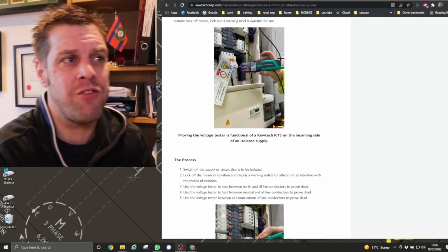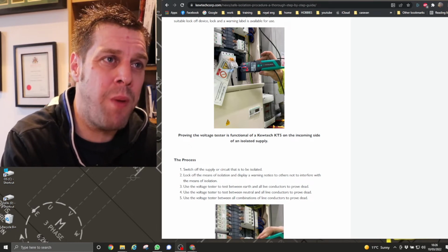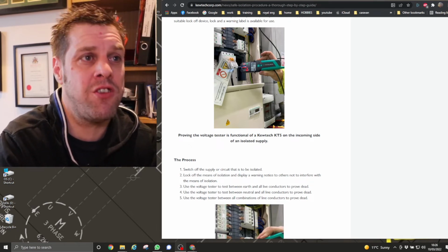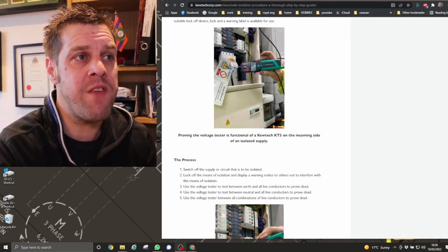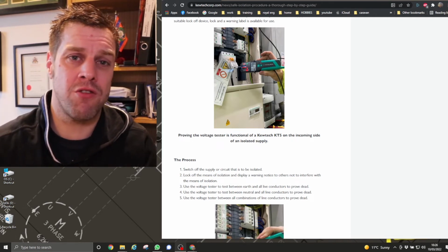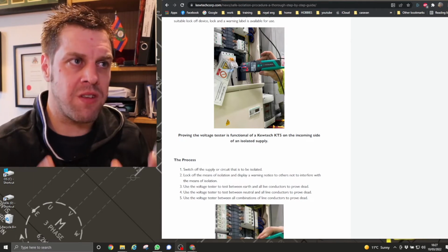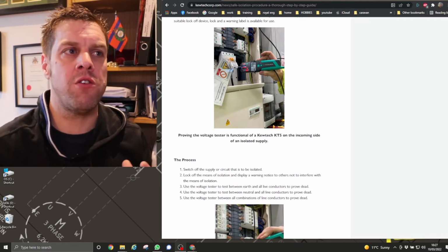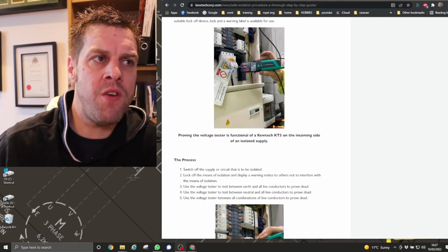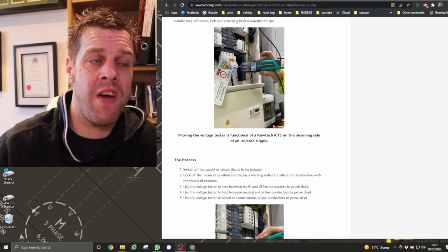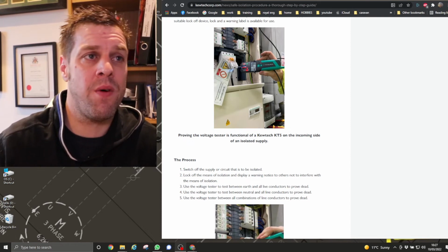I'm not saying people are going to start dropping dead. I'm not saying people are going to get killed, but you're giving a visual representation on your website for everyone to see of this being done incorrectly. When you're in that board, you want to be able to just know that all the board's dead, that you can doddle along doing your job without any risk. Also, you can't leave that board. If you leave that board now, you're leaving live, exposed, conductive parts to anyone that wants to come along.